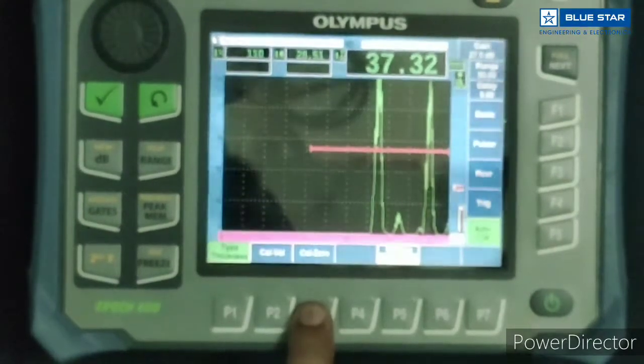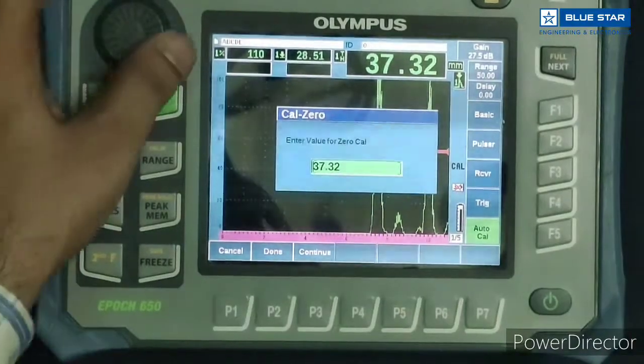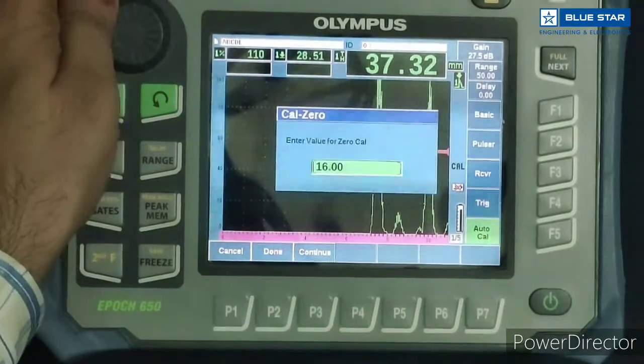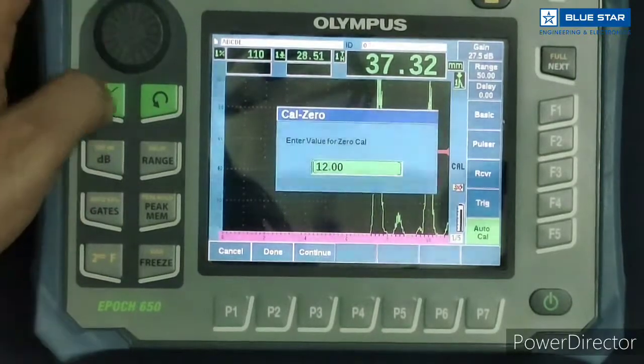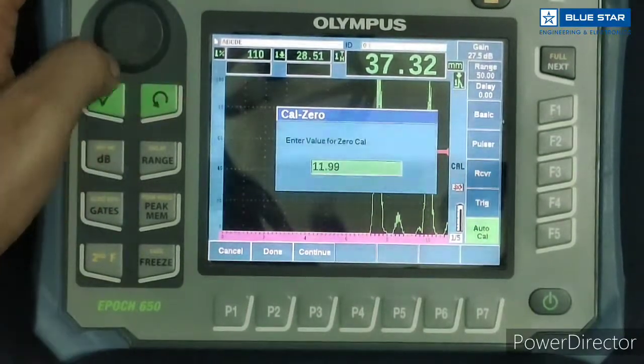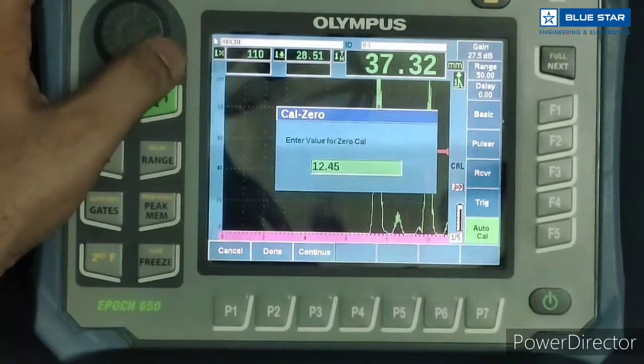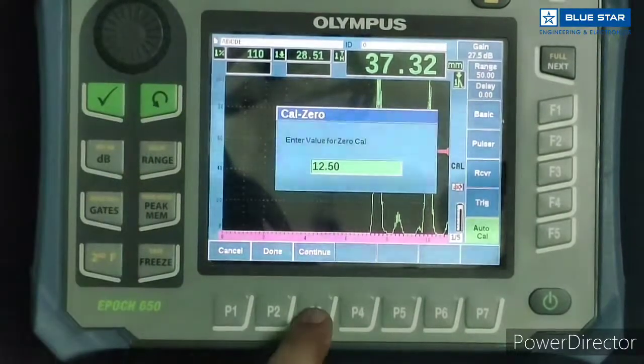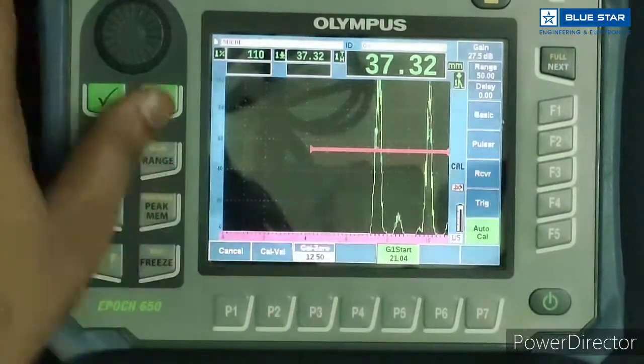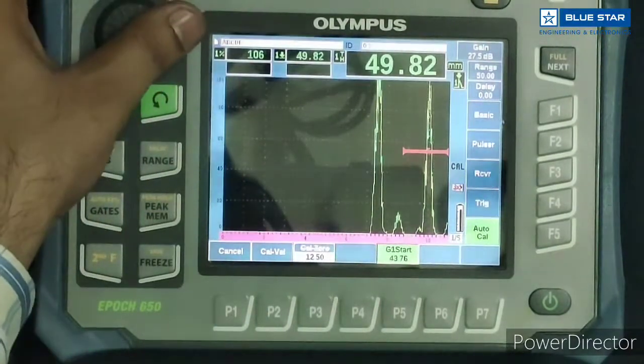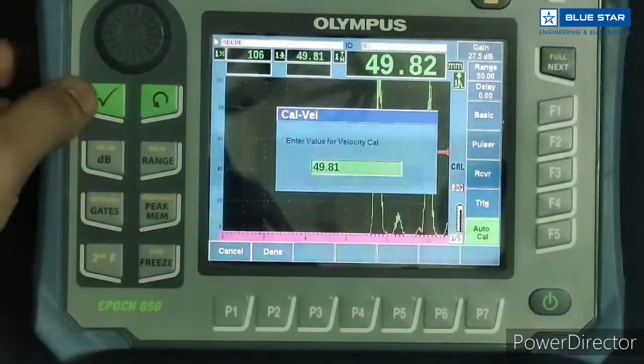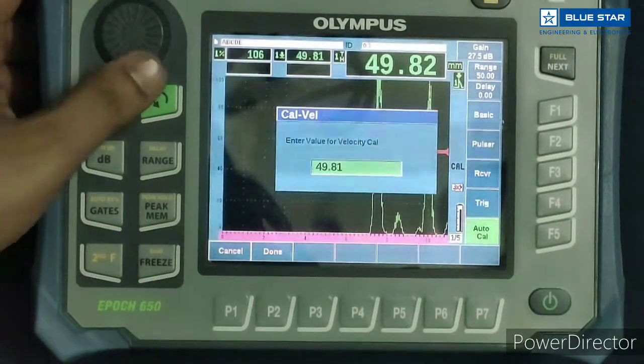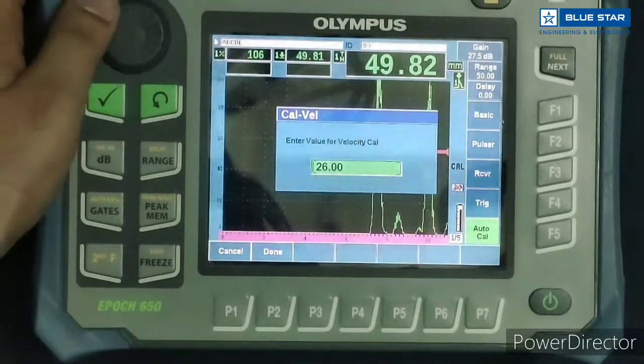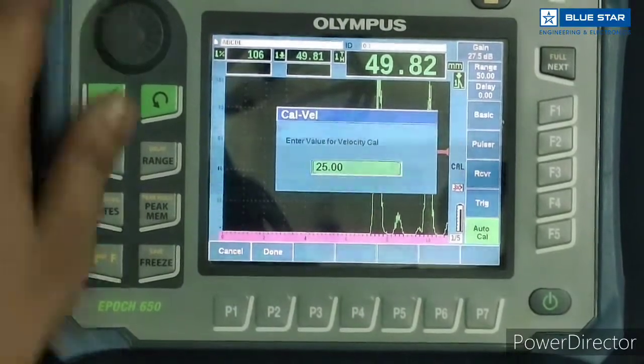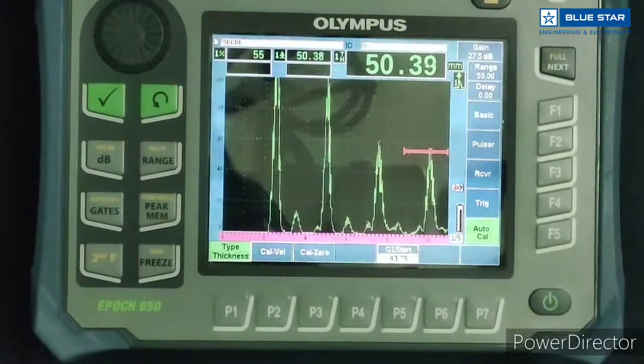Select first backwall indication, press Cal 0, adjust the value 12.5 mm, we are calibrating on V2 block. Press continue, again press gate and go to second backwall indication, press Cal-Vel, adjust the value 25 mm, press done. Calibration is completed.